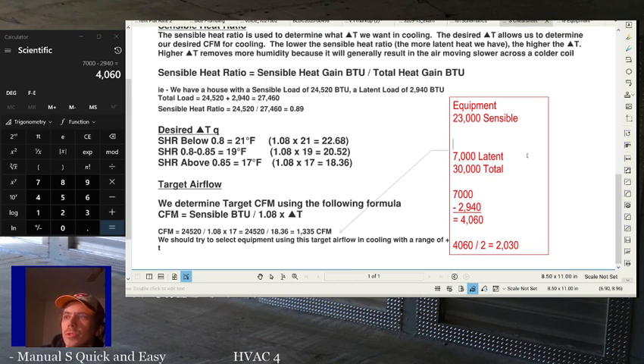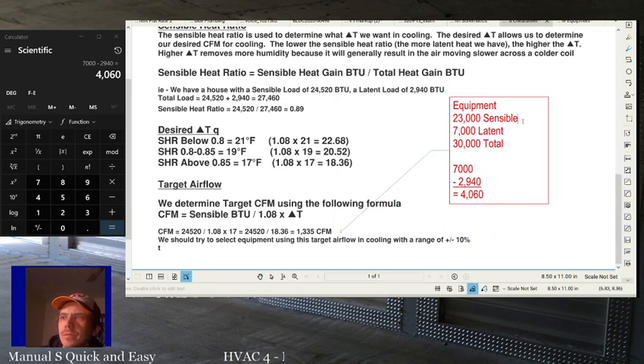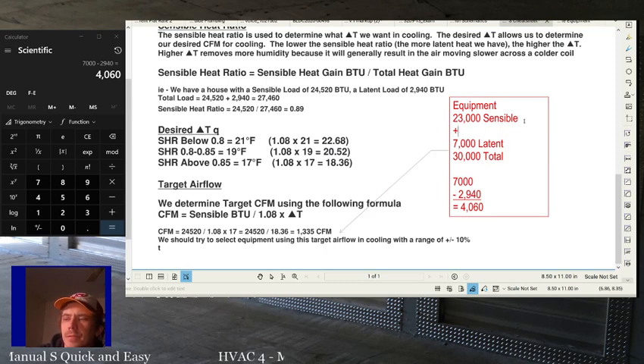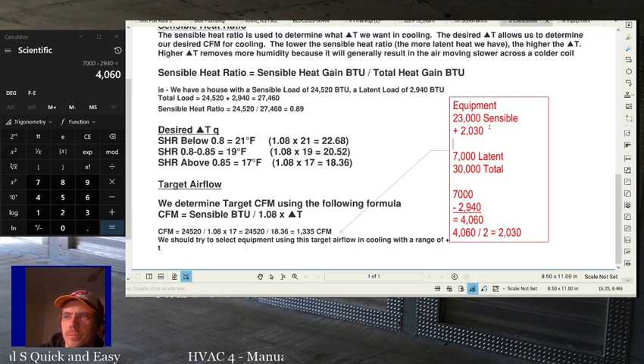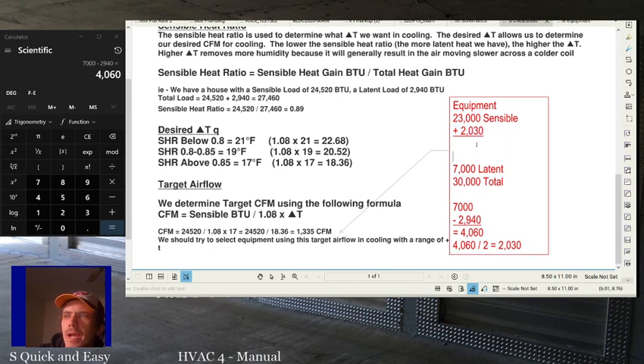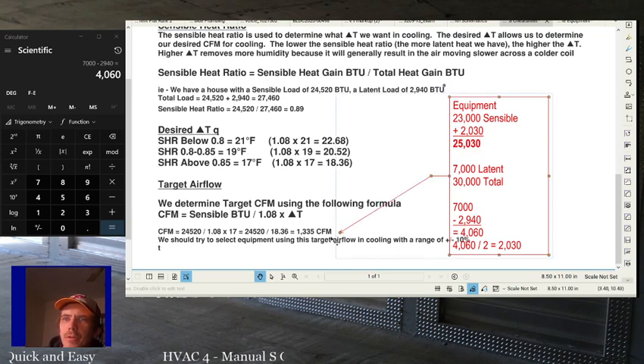So that our new sensible total, what the heck just happened? I must have accidentally deleted something. Alright, let's put that back up there. I've got to put it all back. 4,060. Out of that 4,060, we divide by 2. That gives us 2,030. So we can add that 2,030 to our sensible. Alright. And that means that our actual sensible capacity per Manual S would be 25,030. So now this 25,030 is bigger than the 24,520.